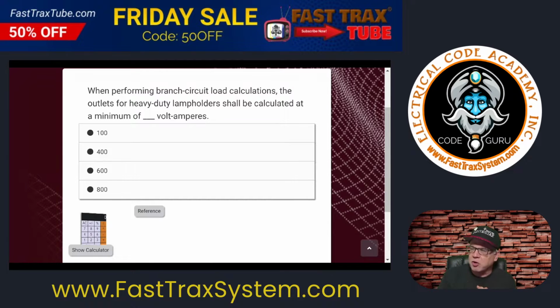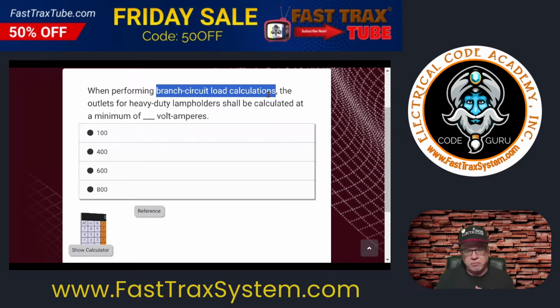And one of the things that I'm looking at right away, and it's telling me is what? It's to perform a branch circuit load calculation. When you see it say something about a branch circuit load calculation, that immediately sends you to think, well, I'm going to be thinking of Article 220. That's calculations. Now, we're not thinking of Part 3 because that is service and feeder calcs. We're not thinking of Part 4 in 220. That's optional. We're thinking Part 2 branch circuit applications, right? So that's where we're going to go.